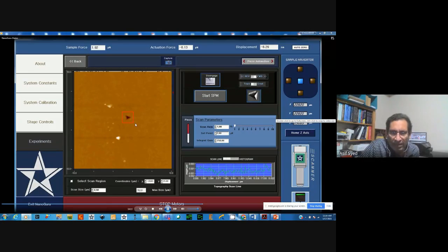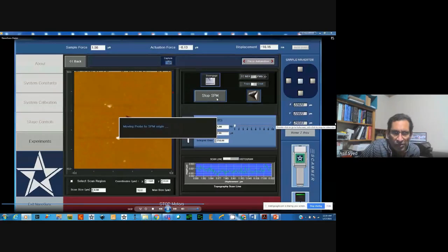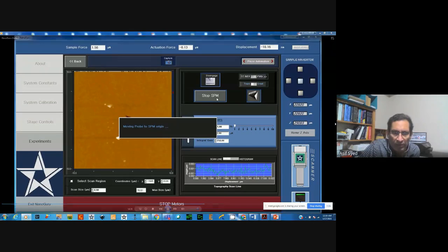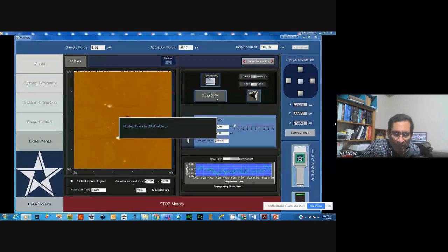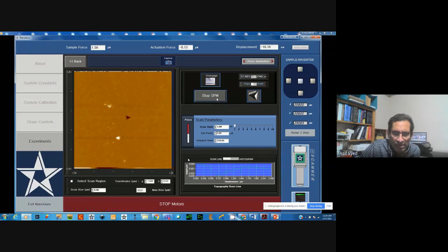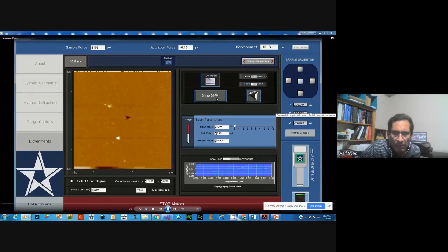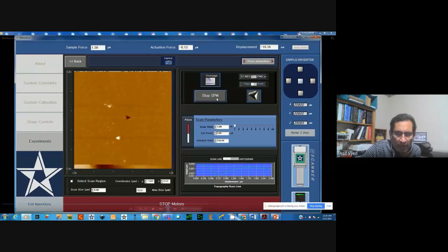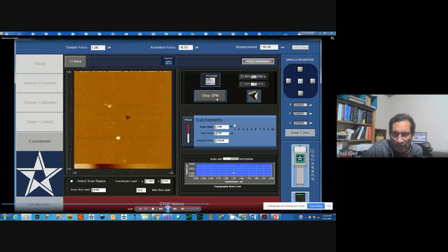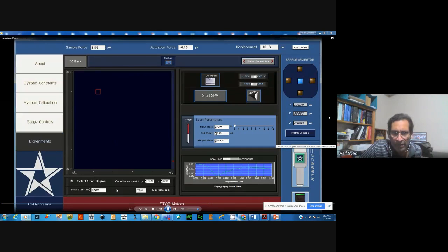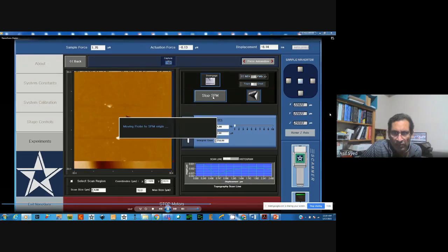You can see a rectangle when you zoom, and then you start the SPM image. Now it will only zoom into that image area, but I think there is an offset, so I'm going to change that by changing the scan size. Okay, I see the offset here now, and on the line by line profile you can start to see the indent. So I'm going to correct the offset, change to a 4 micron image size, and start again.